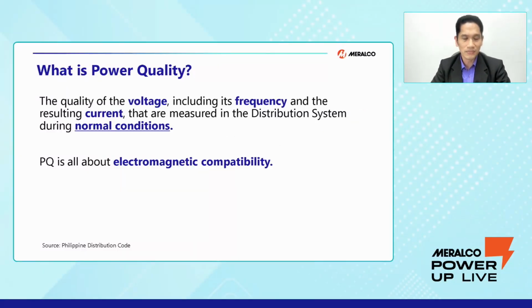Power quality, as defined in our Philippine Distribution Code or PDC, is the quality of the voltage, including the frequency and the resulting current that are measured in our system during normal conditions. When we say normal conditions, there are no typhoons and no supply deficiency. Power quality is all about electromagnetic compatibility. It means that our equipment or appliances will be able to operate satisfactorily without experiencing disturbances from our supply, and without causing disturbance to our system going back to our supply.